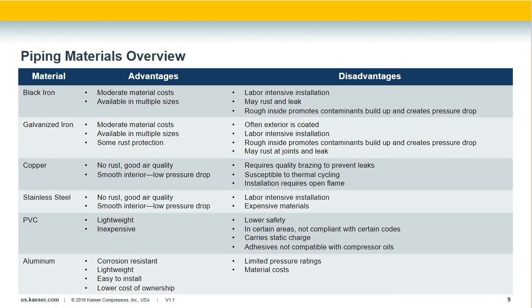Higher pressures cause even higher artificial demand, further increasing energy consumption. Buildup can also pass downstream to the point of use, further affecting product quality. This chart gives an overview of common piping materials and their advantages and disadvantages. A caution: avoid PVC piping for compressed air. It's common because it's lightweight, but OSHA has ruled against above-ground installations unless encased in shatterproof material. For reliable, cost-effective piping, consider aluminum or copper. Food and beverage manufacturers often specify stainless steel — a good option, but labor-intensive and expensive to install.